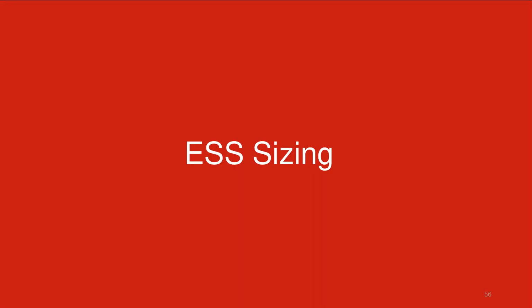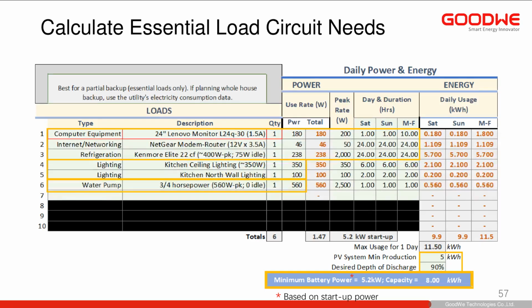So now you've got your load profile, you want to size systems. A simple way to do it, well, it doesn't look simple here, but I'm not going to do all the circuits. We're just looking at an essential loads panel. So it's a few circuits, so it's easier to do by hand, or in this case, a spreadsheet. Each of the lines here represents a different load, but the gold rectangles represent what circuit they're on. So there are really 3 circuits I'm backing up, right? And that's mostly the case. You're backing up circuits, and so you need to know everything that's on that circuit.